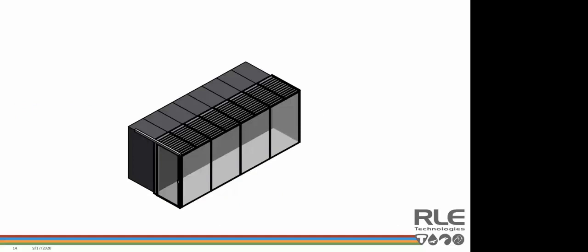And finally, this is also pretty typical. You can often find an aisle without a corresponding row of racks. And for containment solutions, this requires that an entire side of the row be filled with containment. There are some standard non-custom solutions available on the market to contain aisles, but these solutions typically require that row ends be exactly even and really work best when rack heights are all the same. They also don't usually fully close off the top of an aisle completely, which lets some air escape out of the aisles. So for all the examples we've just reviewed, really custom containment solutions are required to provide the best and most complete containment of an aisle or row.